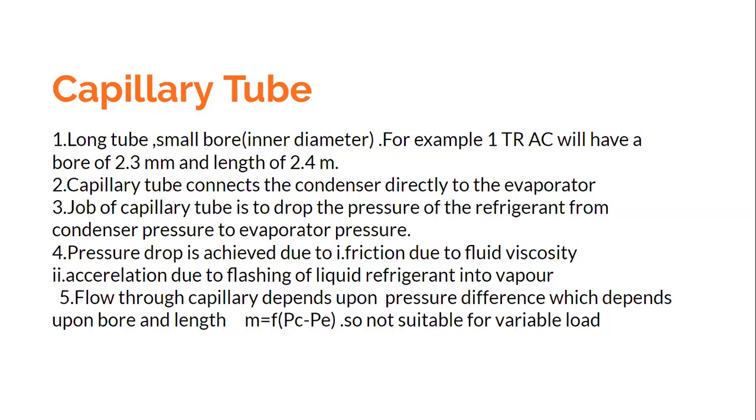So the exact length is given here, 2.4 meters. The typical bore, the typical inner diameter of that tube, is very small. Look at this. How much is that? It is about 2.3 mm. So the bore is in mm and the length is in meters. That gives you an idea about the capillary tube.